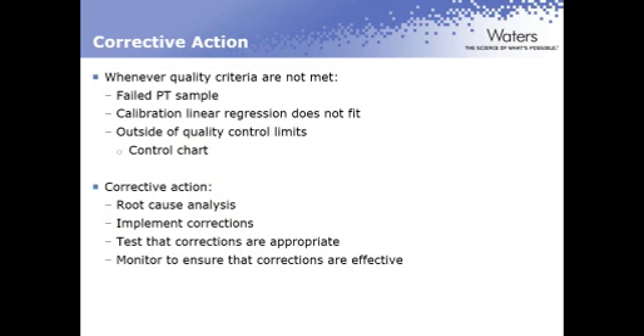Here's a few examples of that. A failed PT sample. That's when we run something blind and the result that we report back to the PT provider is outside of the acceptable ranges. When the calibration linear regression doesn't fit, let's say we're running a 3 or a 5-point curve, and it doesn't meet our correlation coefficient, we need to do some corrective action to find out why. Also, we need to do it when anything is outside of the quality control limits. That's where your control charting comes in. Once we get data points outside of that control chart limit, or if we see trending, we see 5 to 7 data points consistently going up, consistently going down, that's a trigger that corrective action is needed.